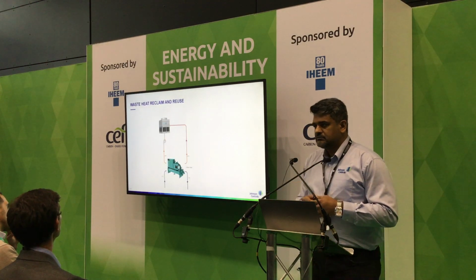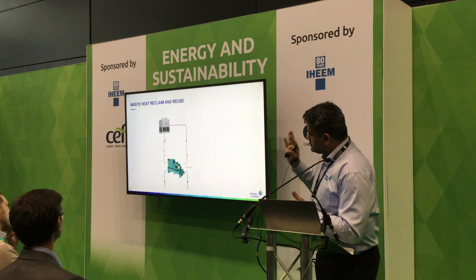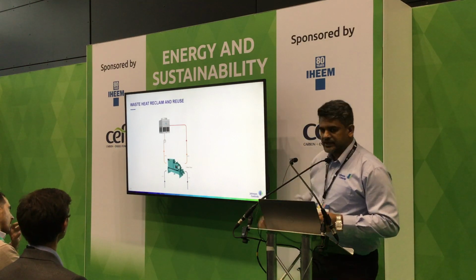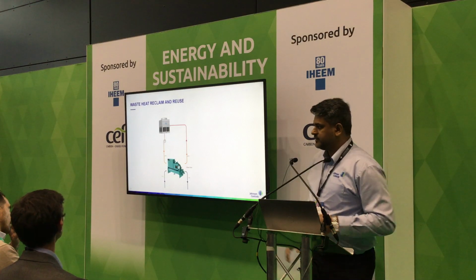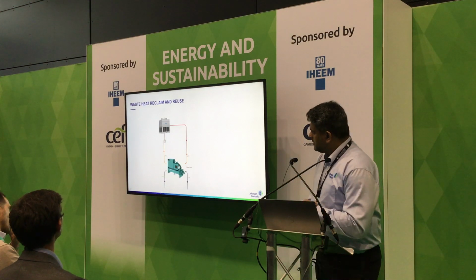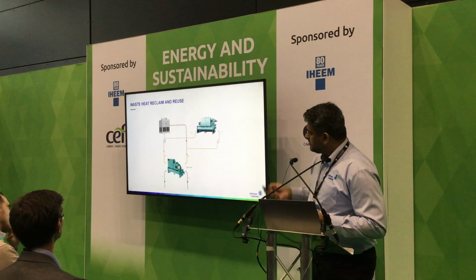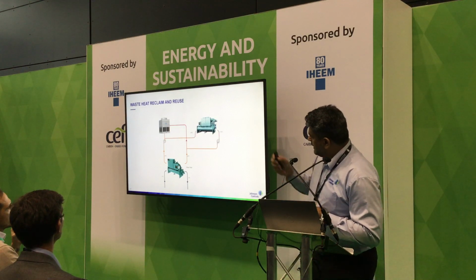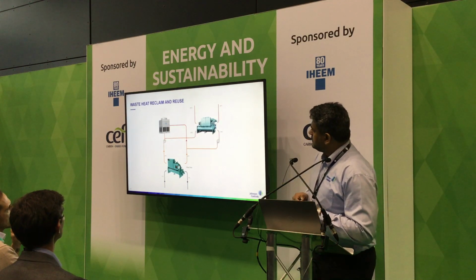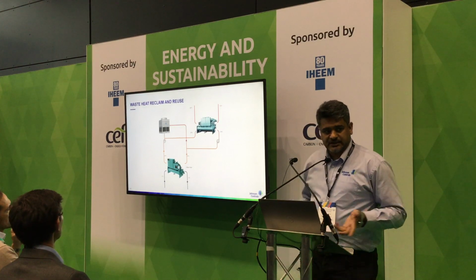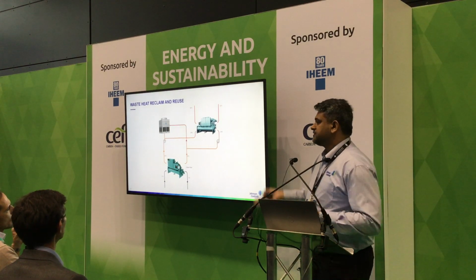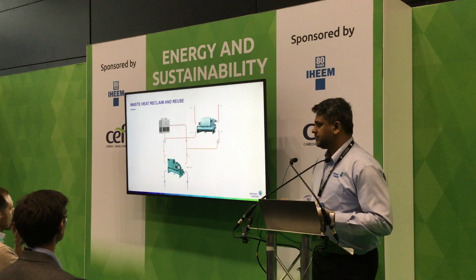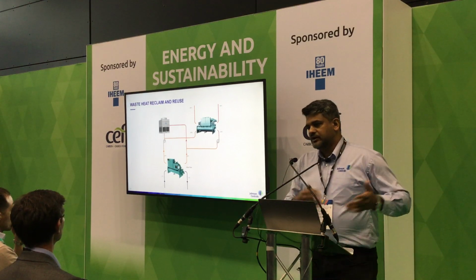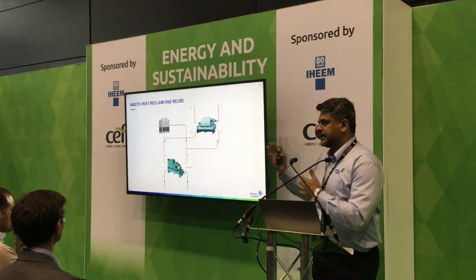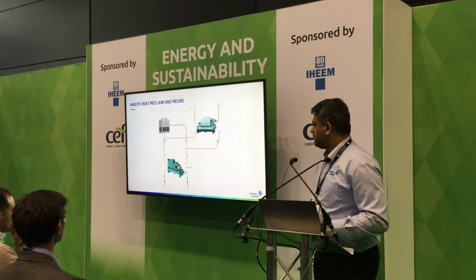Waste heat reclaim. Typically your chillers would reject heat into a cooling tower, which is then just dissipated into the atmosphere. So that's energy just wasted. If we plug in a heat pump onto that condenser or heat rejection line, you can actually deliver hot water temperatures up to 80 and completely offset your boiler. So another example of using heat or energy that was otherwise wasted and bringing it back into useful application.